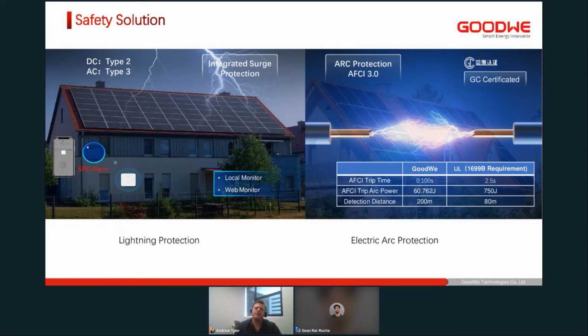And then on the right, we spoke about AFCI briefly earlier, but you'll see that our AFCI is well ahead of the requirements for the UL certification, such as the trip time, the arc power and the detection distance. We really are superior to the requirements, which should give you comfort for those markets where it's required.